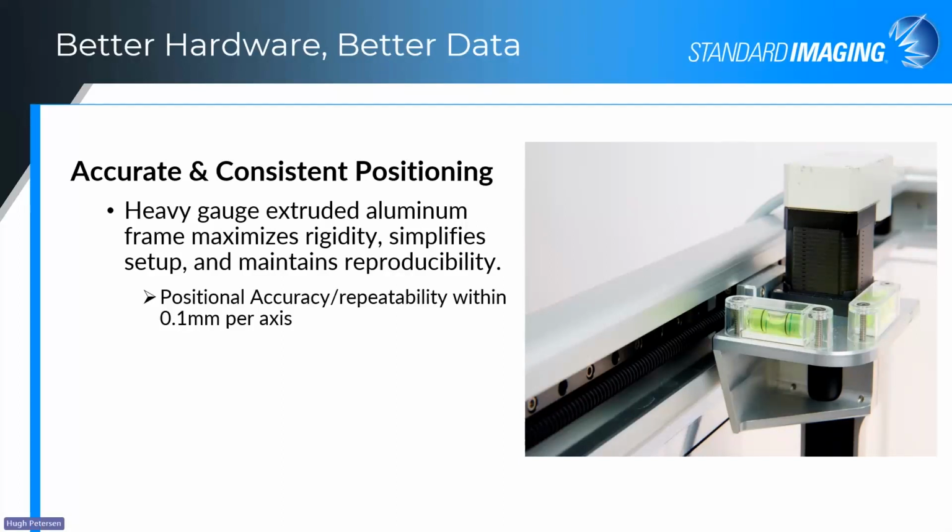Positional accuracy and repeatability is within that 0.1 millimeter per axis accuracy. So it's a very accurate system and very reproducible. Sorry about that. We allow for a very quick 3-point leveling, and I'll touch on that as well in a couple slides down the road here. Just talking about some of the accessories we offer to make that alignment and setup very quick.